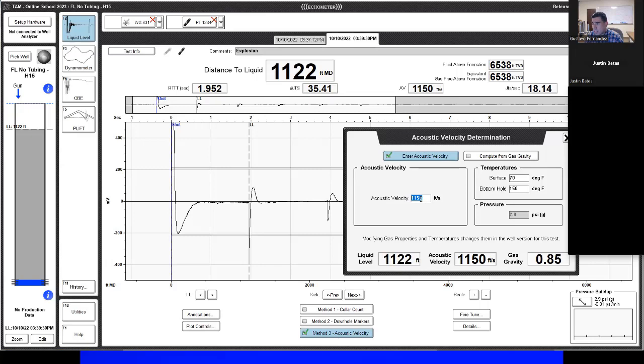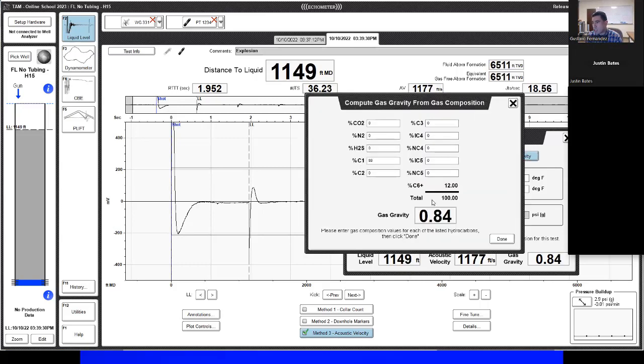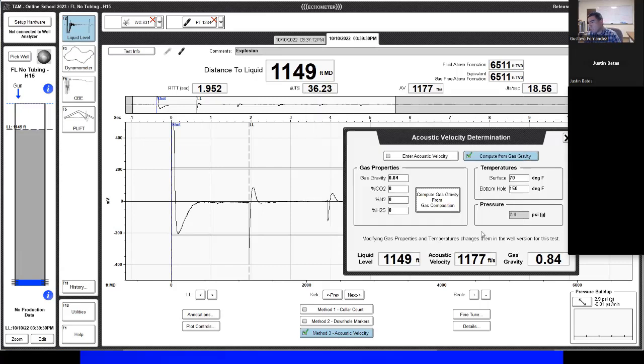So we know the acoustic velocity will be around 1150, 1140 to 1170 when hotter, fluctuating a bit based on temperature. This is one scenario where you don't know the gas composition, and by default in the software it's set like 88% methane plus heavy components - this is not real. We can enter the acoustic velocity, and based on temperature you can slightly adjust it, but it won't make an important difference.